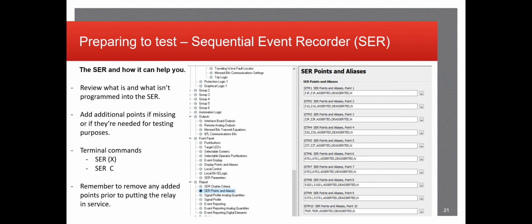The SER will also show you if you're missing something. Again, if your test isn't set up correctly and the output's not operating, you'll see in the SER that that specific output never opened or closed. SERC is the terminal command to clear it. SERX, X being any of the relay elements, outputs, anything like that. Those will show you whether or not those operated within the last however long until it was previously cleared.